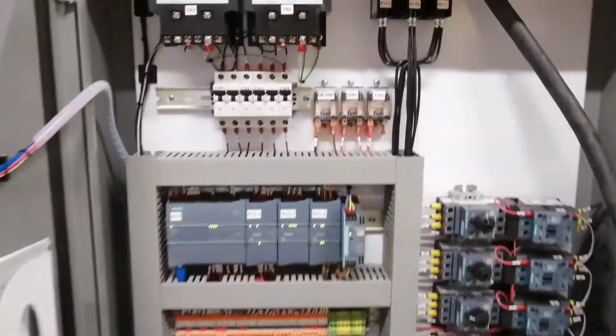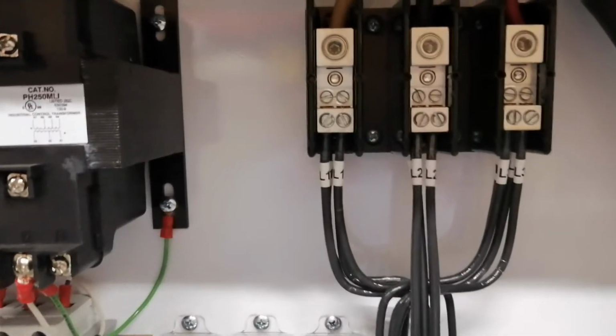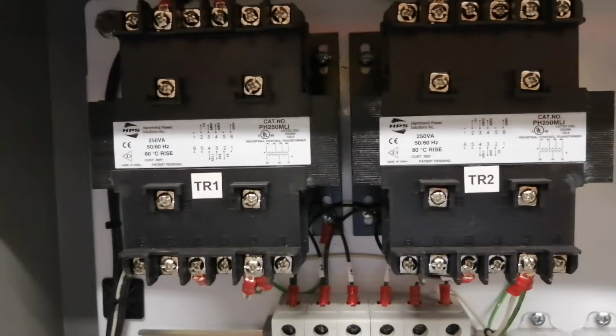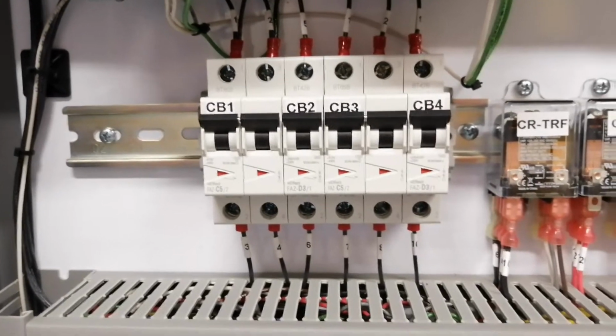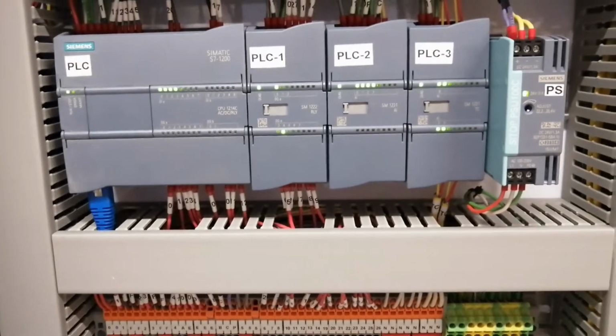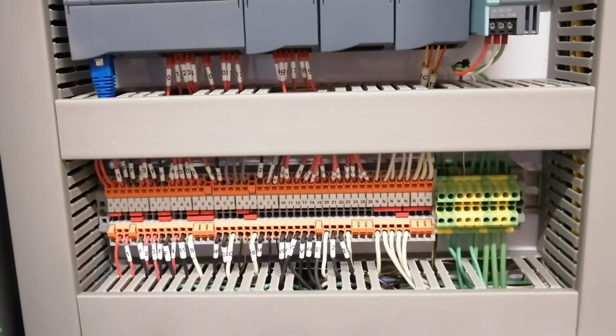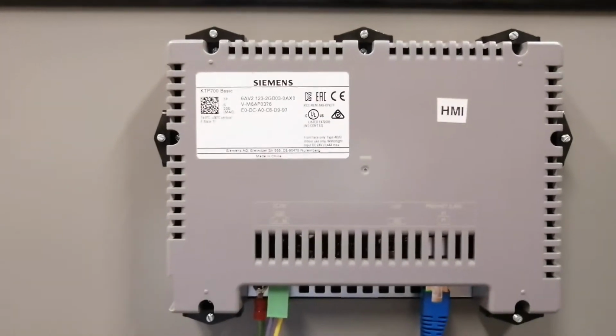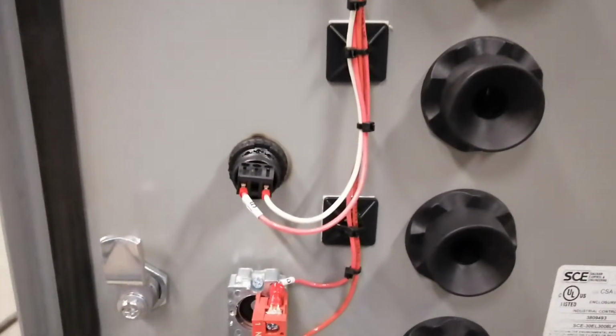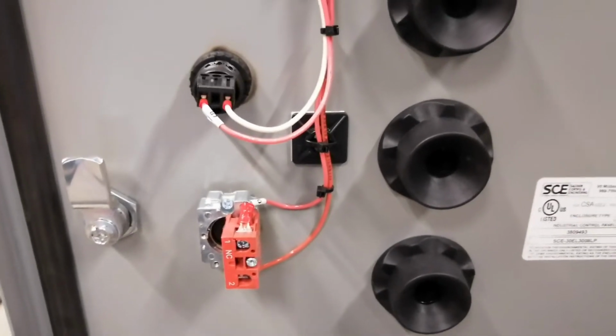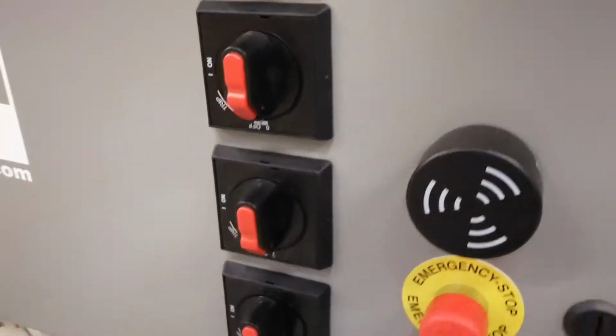The control panel is provided with the distribution block, control transformer, dual control transformer, primary and secondary circuit breaker, control relays, PLC depending on the system, control blocks, ground connectors, contactor and MCP for each motor. In this case, the HMI, the alarm, and emergency stop button are shown in the front panel.